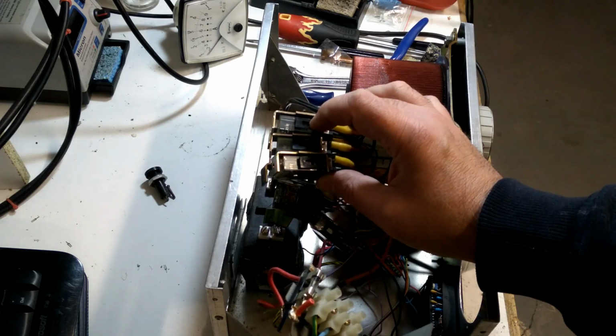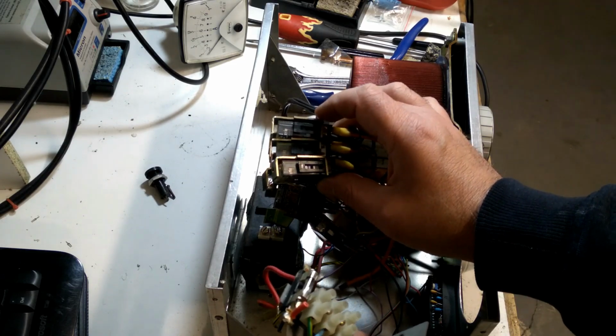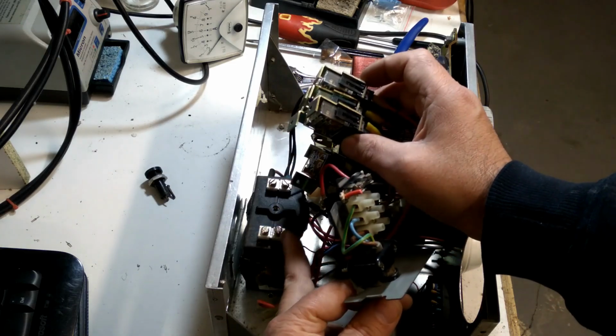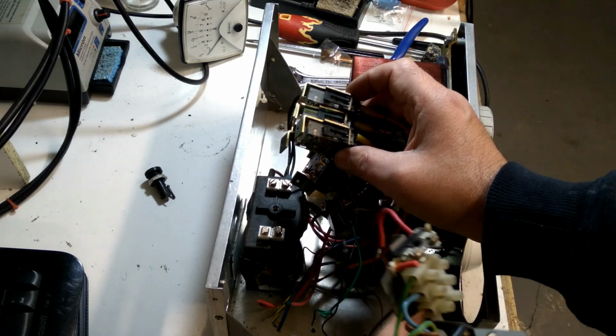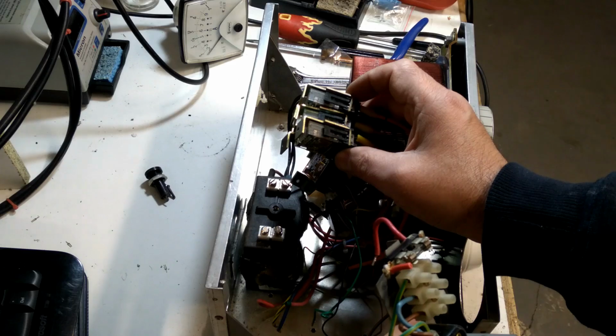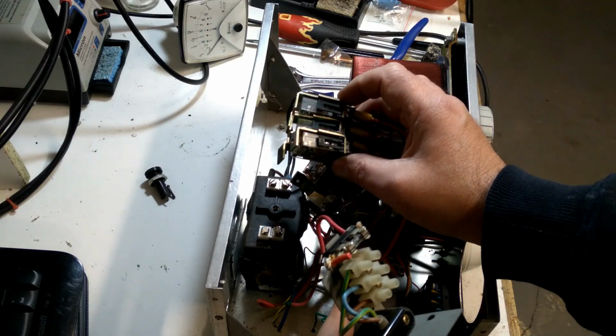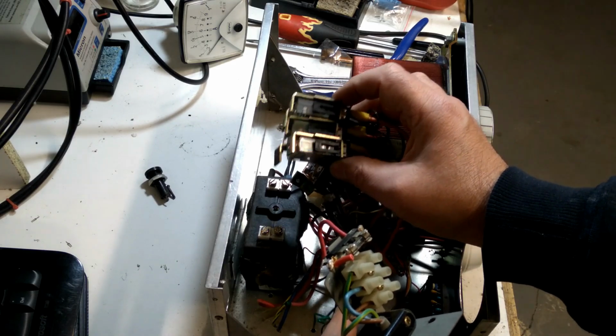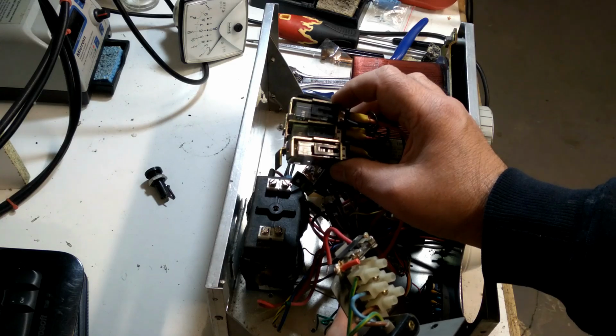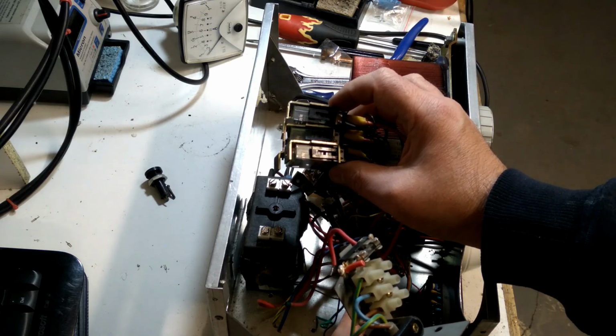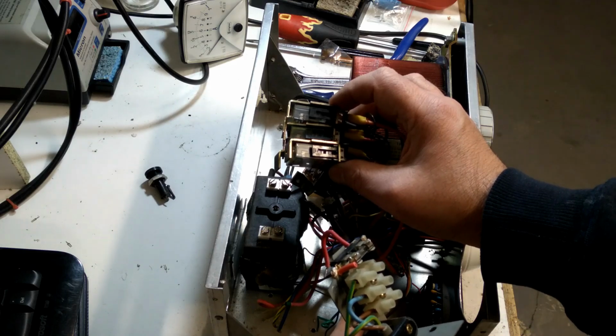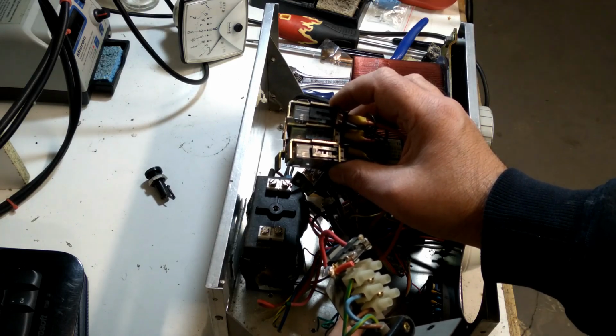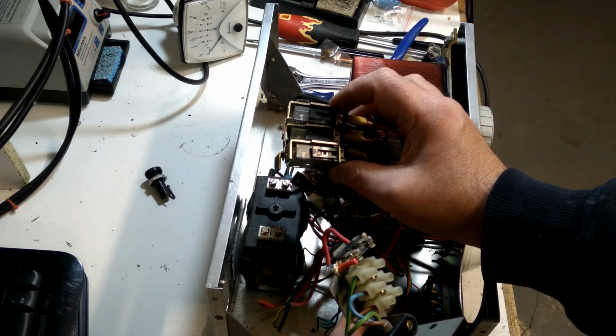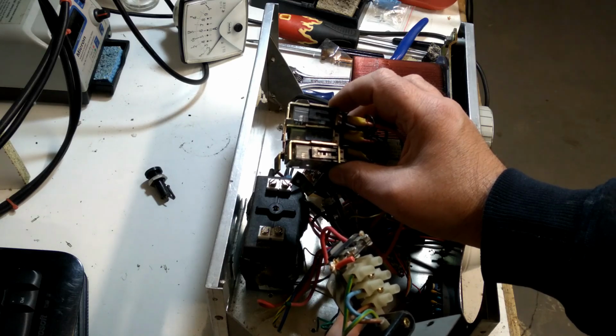So because it's in series with the primary of the current transformer, it's going to show me what the actual current is, always what the actual current is running. So that's why I chose this system - I'm always going to read the accurate current. If you don't do it this way, if you have bad contacts when switching from one scale to another, you'll get an error on the actual current of the load you've put on.